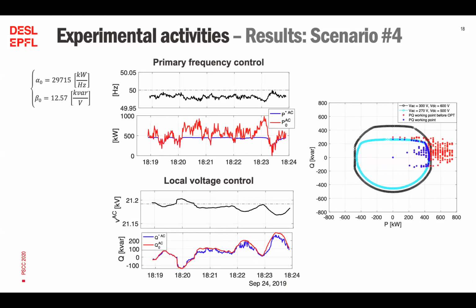Similar considerations are valid for scenario number 4, where even more aggressive droops are used. In fact, we can see that for almost the whole duration of the test, the initial set points are falling outside the feasible region, but still we could manage to provide continuity of the service delivery.